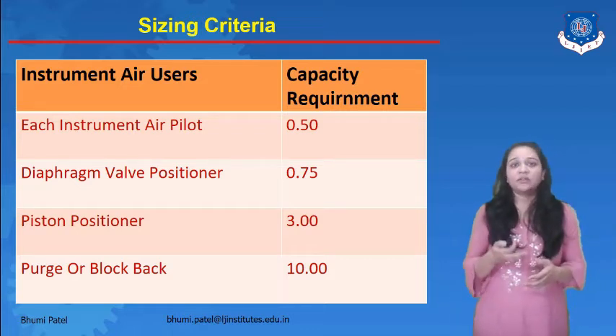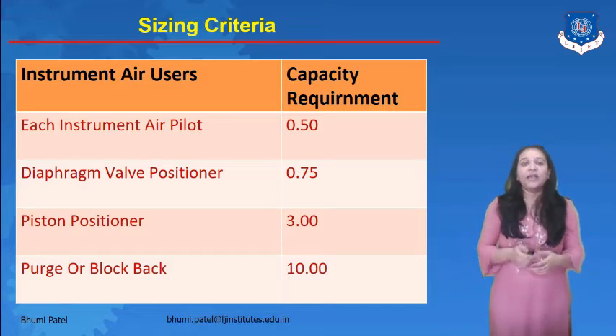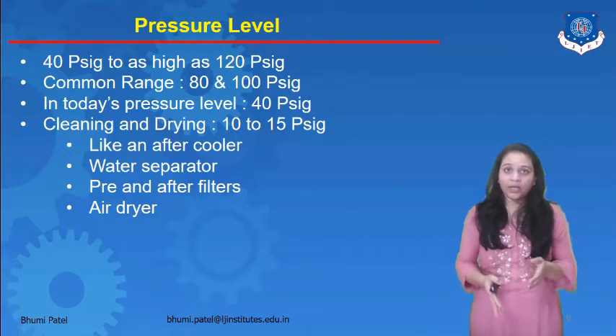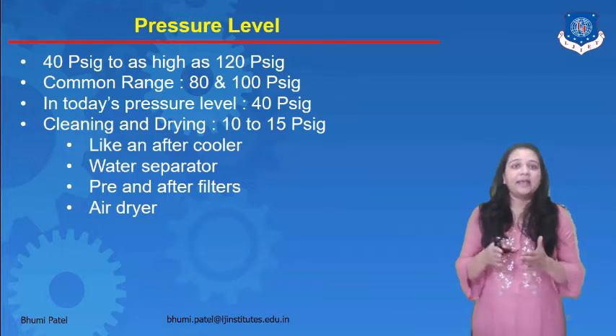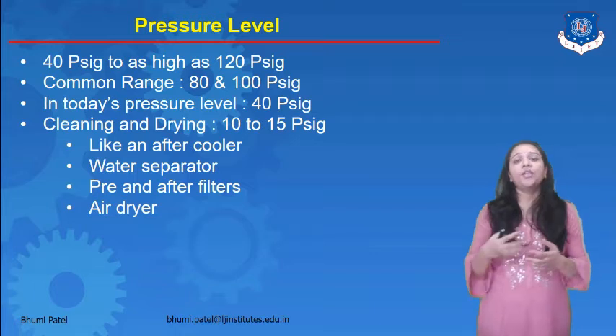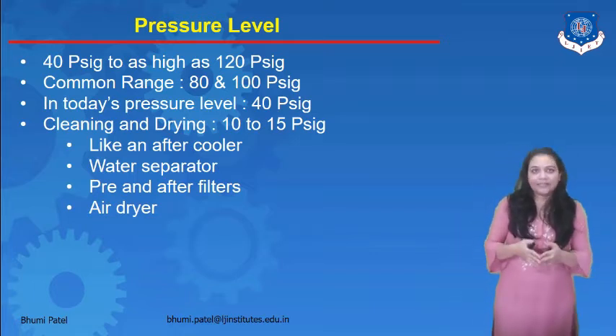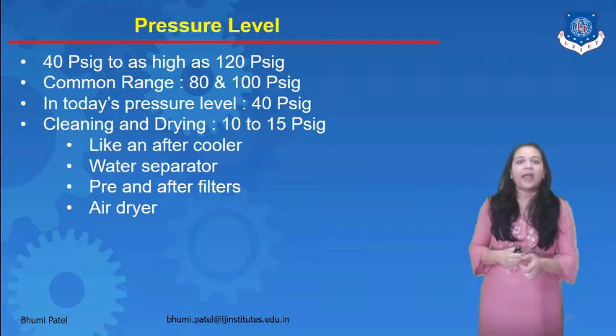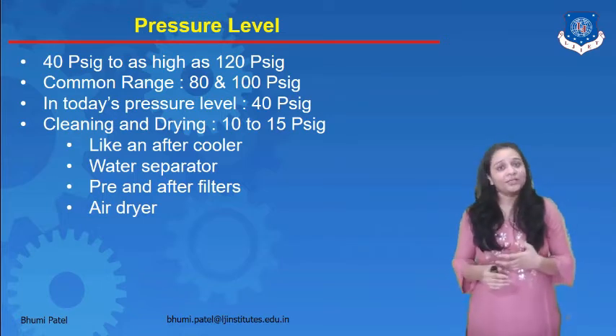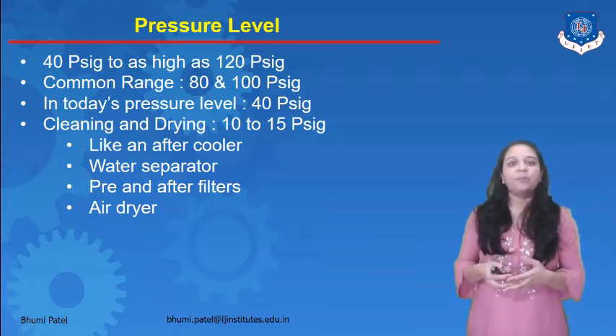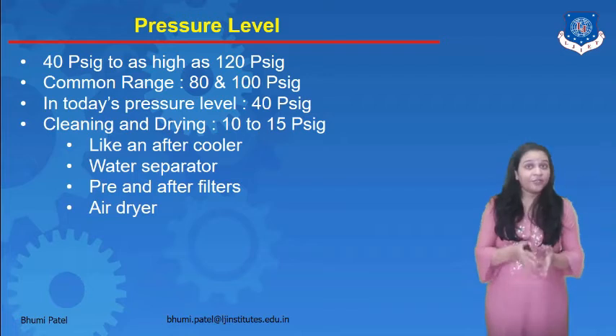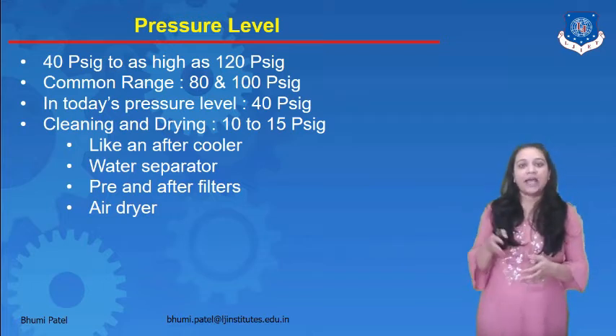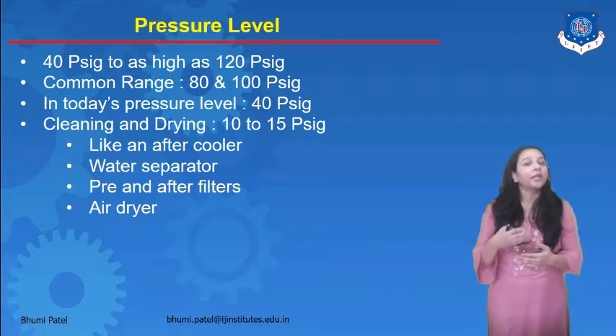In our syllabus, we have studied four types of instrument air users. The next factor is the pressure level. The pressure level range for a particular instrument is 40 PSIG to as high as 120 PSIG. The common range of the pressure level is 80 to 100 PSIG. In today's instrument systems, we generally use a 40 PSIG pressure level.